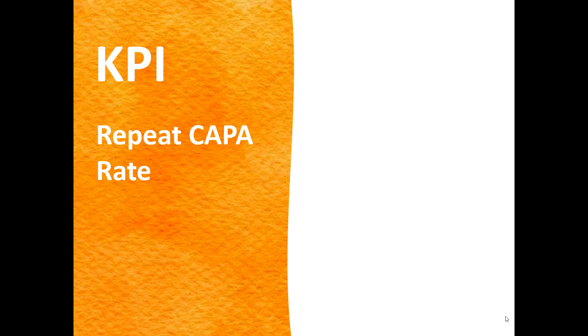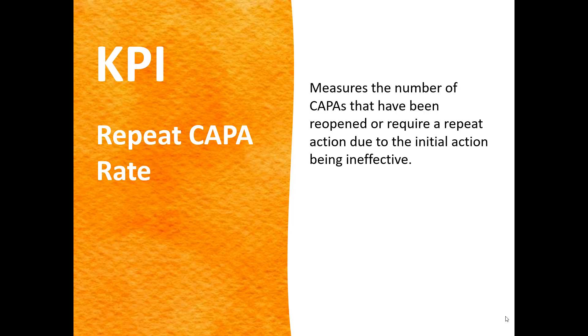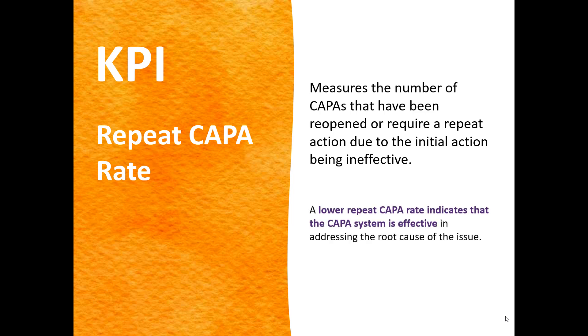You also need to track the repeat CAPA rate — this is a very important one. This measures whether CAPAs have been reopened or required a repeat action due to the initial action being ineffective. This is the case where you had a CAPA, worked on it, closed it out, and then the issue re-occurs — requiring you to reopen the CAPA or open a new one. A high number of repeat CAPAs means your CAPA system is not working. Did you not get to the root cause in the original CAPA? Were the fixes put in place not adequate? CAPAs cannot be closed until the effectiveness of the corrective actions has been monitored, so if you have to reopen a CAPA, something went wrong.